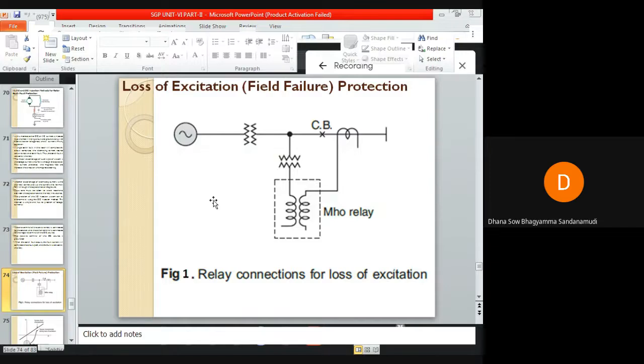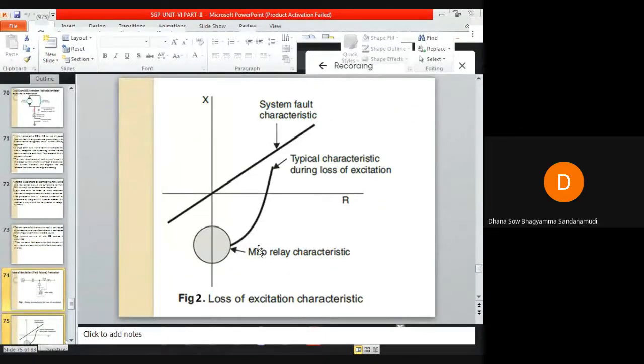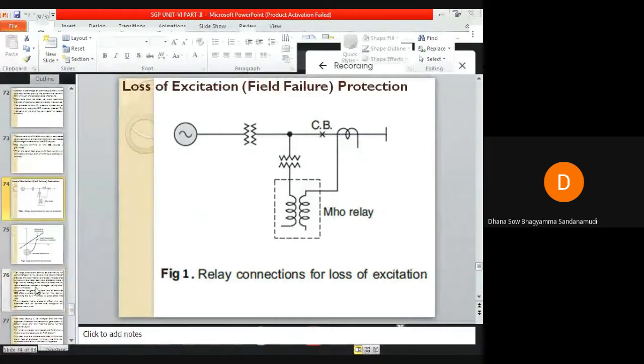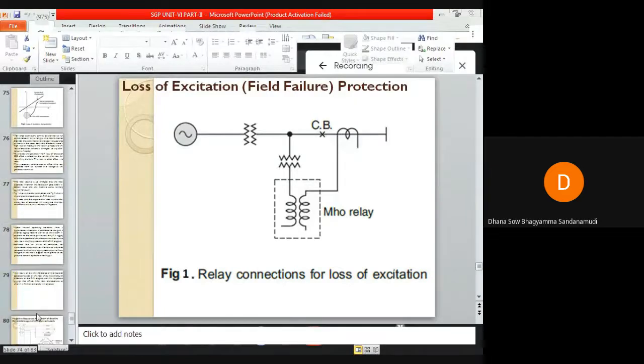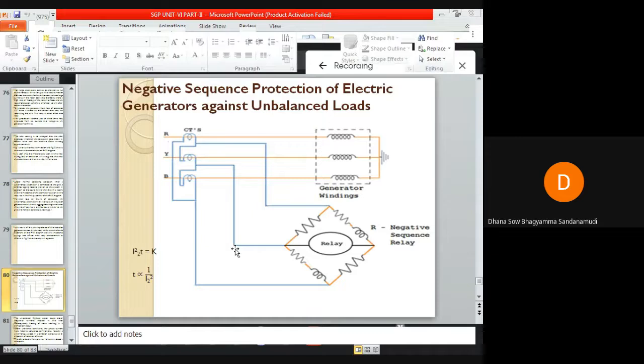So the impedance characteristics of this synchronous generator will shift to the fourth quadrant, and when these characteristics swing into this Mho relay characteristics, the relay will operate, and the circuit breaker is opened. So this is the loss of excitation protection of your alternator. Now let us see negative sequence protection of this alternator under unbalanced loads.